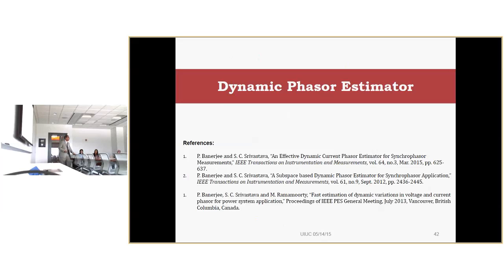Now, dynamic phasor estimation is important in the current context because most of the applications are under dynamic conditions. When the 2005 Synchrophasor standard came, it only outlined the requirement for steady state operation. But in 2011, the major revision came to bring out the requirement under dynamic variations. I'm not talking about a few microseconds or milliseconds, where a transient period is there, but oscillations, basically oscillation monitoring. So phasor calculation becomes tricky there, because the fundamental frequency is always changing, not only at one place, every place. And also you have a lot of DC component and multimodal components present. So how to extract the phasor waveforms?